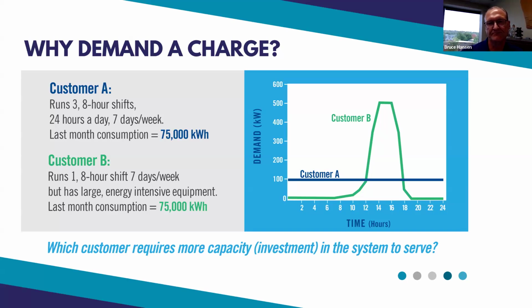I'll add that this really impacts the customer from a billing perspective as well. When they hit their peak demand, that's what they're billed for, off the peak KW they hit on a monthly basis. KWH is measured throughout the entire billing cycle, so these are really two different bill components. When we talk about load factor, having more kilowatt hours spread across that peak demand lowers the cost per KWH as well.